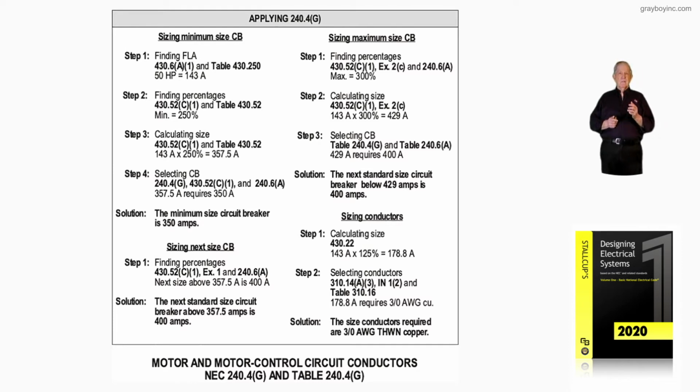So using that 3 times rule, sometimes the electrician or engineer would just take step 3 and round that up to an even unit number, up to 400, divide that by 3, and they would use a 150 amp device there. Now, that's up to the designer, the installer, and so forth. All I want to point out is that the table just gets you started. You can always drop below.